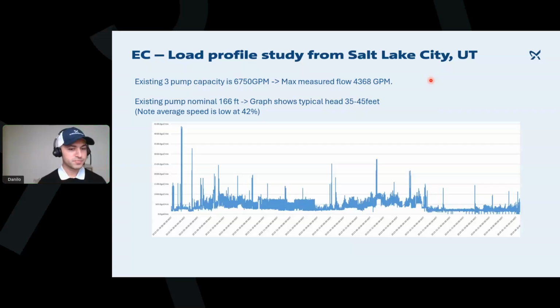This is a building where we did an analysis on the data. So we have three pumps. It's a three-pump system. And the capacity for them was 6,750 gallons per minute. What we measured after looking at all the data from their BMS system, the max flow measured was 4,368, right? We're looking at 2022 all the way to summer 2024. So we have about 2.5 years of data here, and it never reached the 6,000 gallons, right? This is the max flow registered.